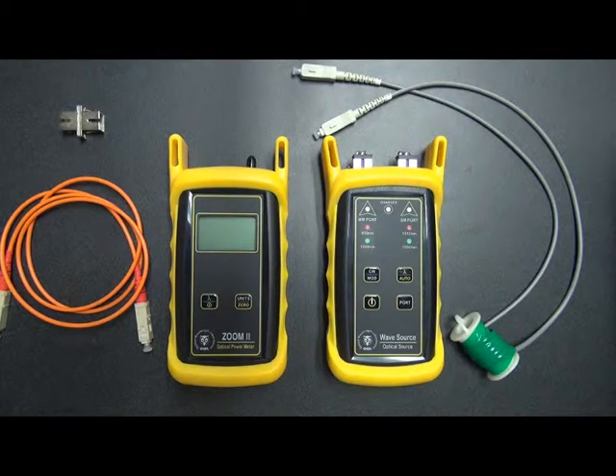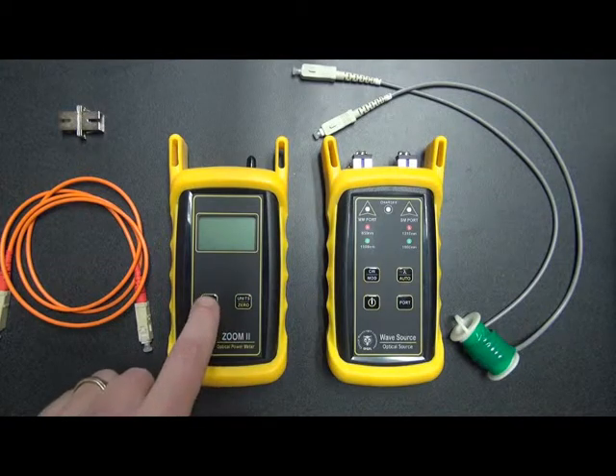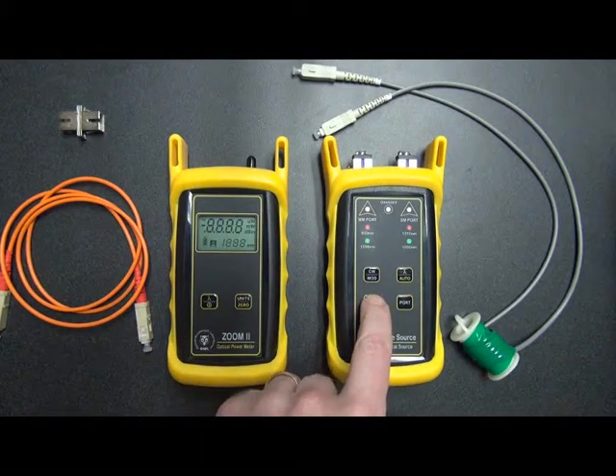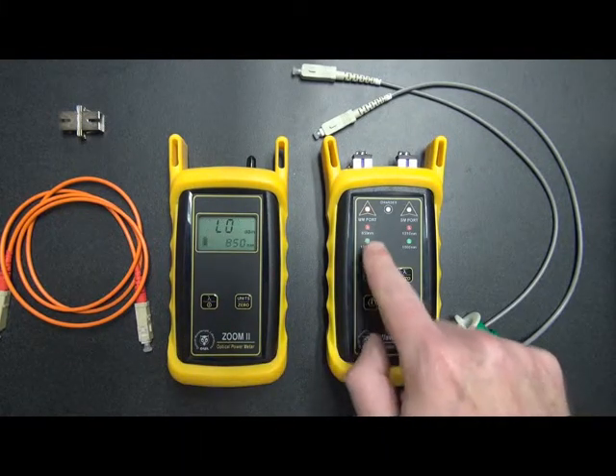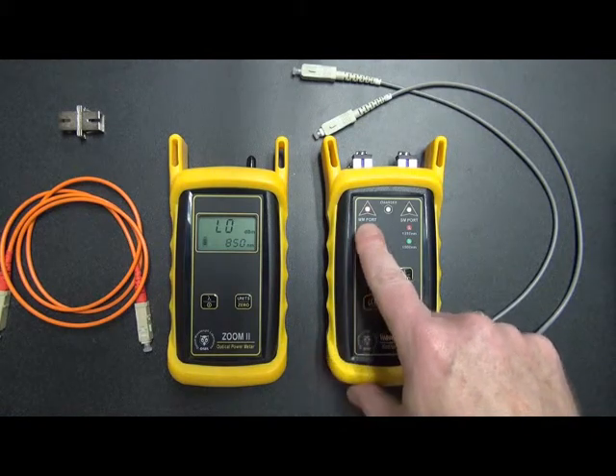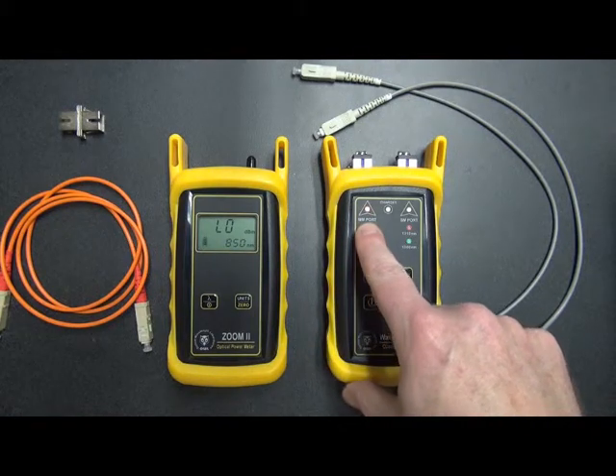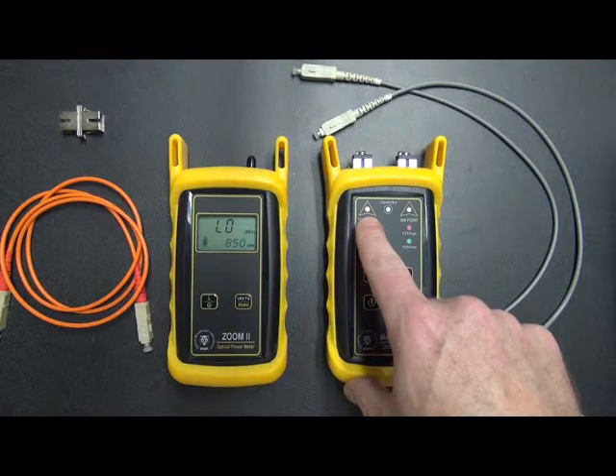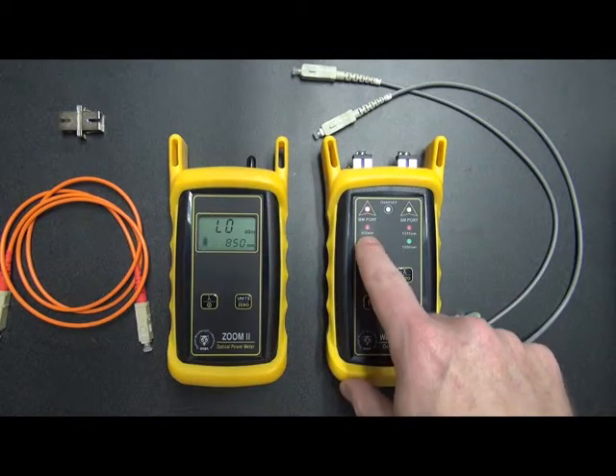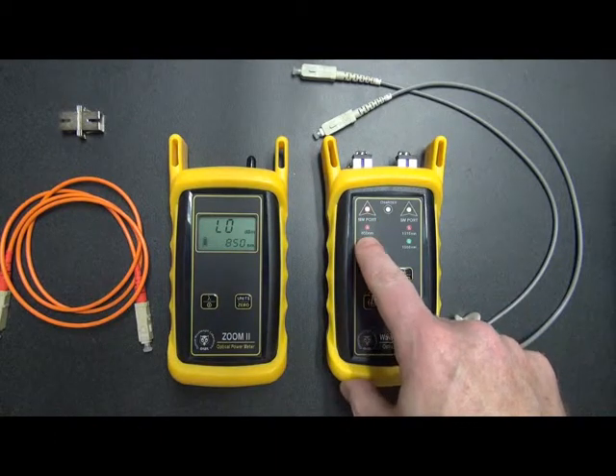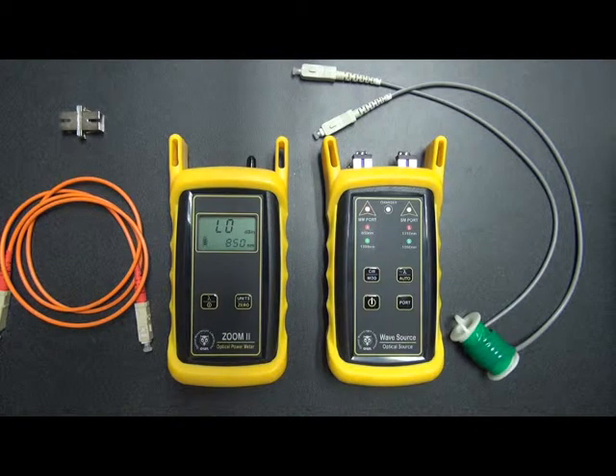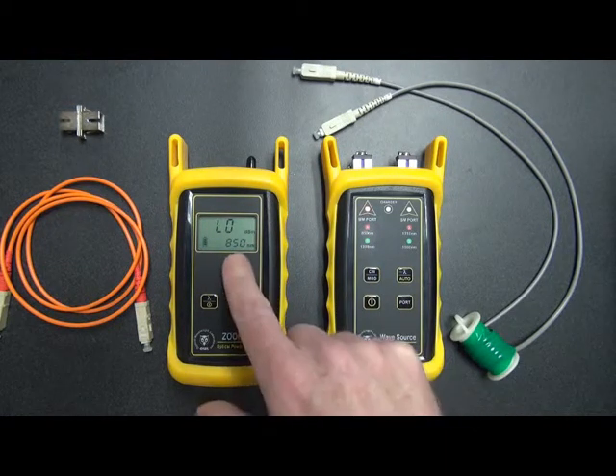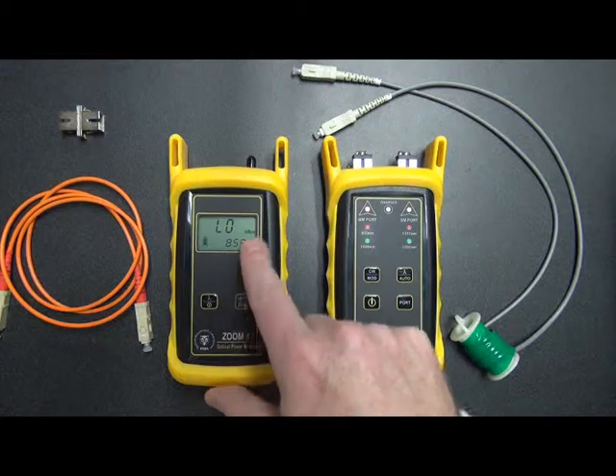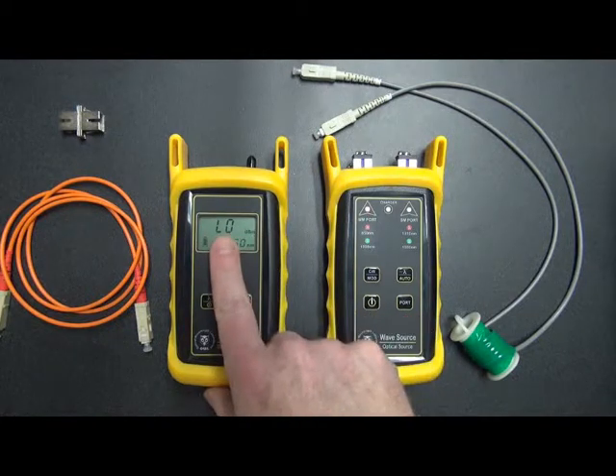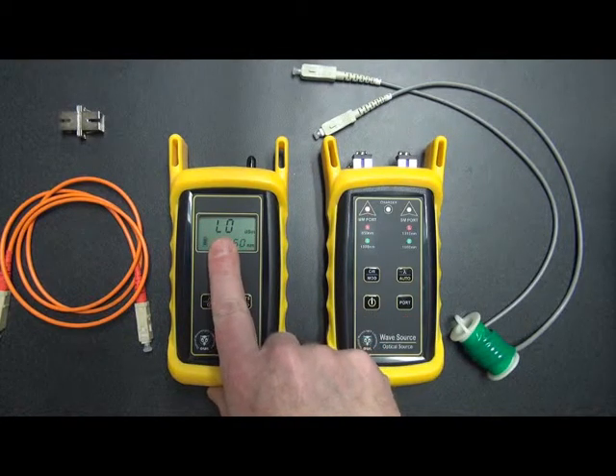The first step is to power on both testers. So we press the power button on the Zoom and the power button on the WaveSource. You will notice that the multimode port is lit by default. You may not be able to see it very well, but the indicator LED here is red, which indicates that 850 nanometer is being output at this moment. On the Zoom, we look at the display and we see that we're set to 850 nanometers, set to dBm, and that our reading is low.